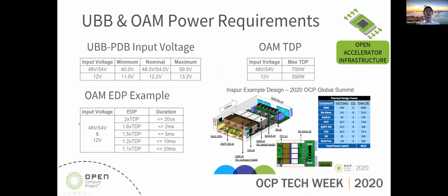Next one, please. And here is a general introduction to the UBB and OAM power requirements. We have the UBB and PDB input voltage listed here. For the 54/48 volt, the UBB and PDB will support from the minimum 40 volt up to 59.5 volt. And for the 12 volt, we'll have the range from 11.0 to 13.2 volt.